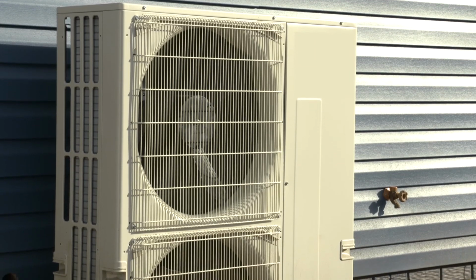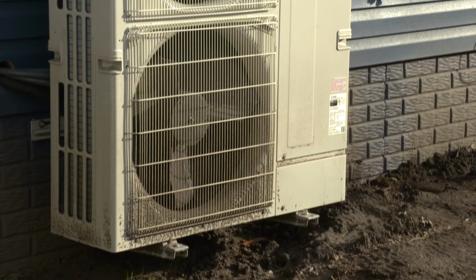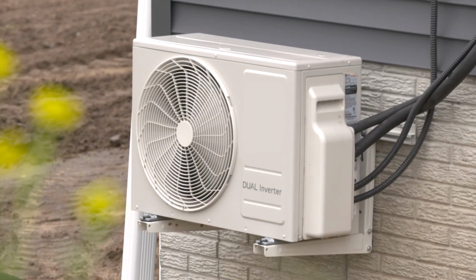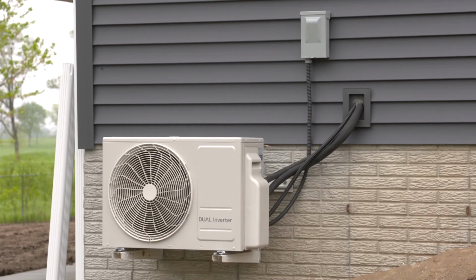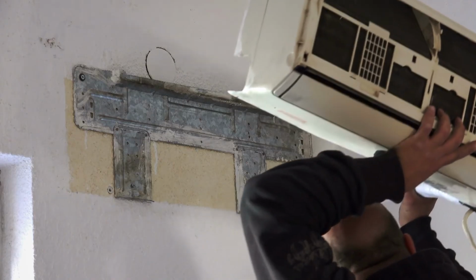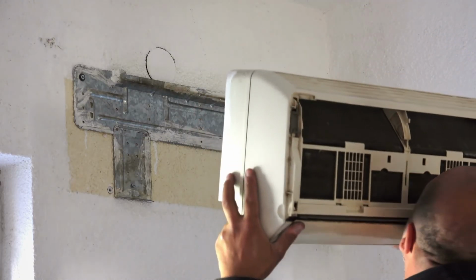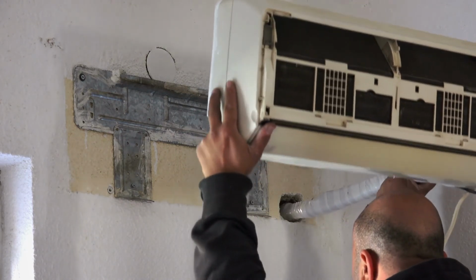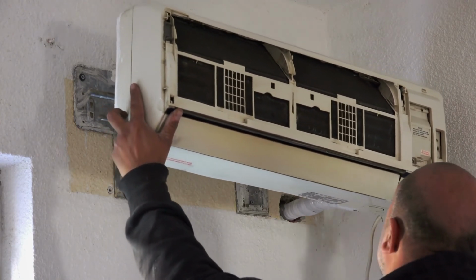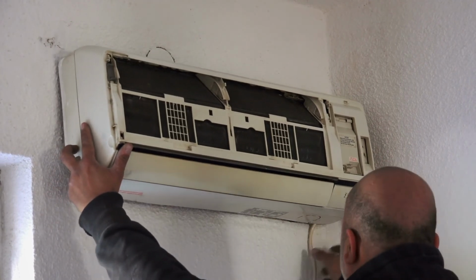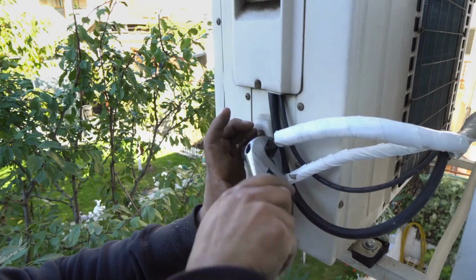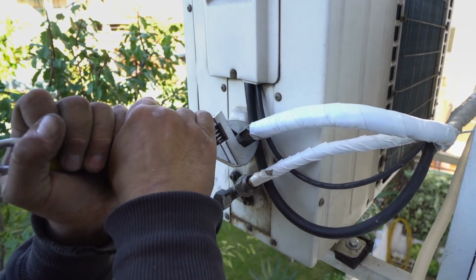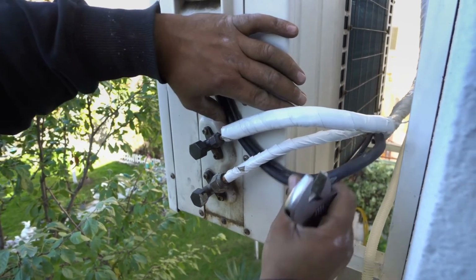Why don't you walk us through the installation process so we can get a better picture? Sure, so we'll look at where we're going to be mounting both units. On the outside of the home, where the condenser or heat pump sits, we'll either install a stand on the ground, or mount a bracket if there's a structure available — you'd see that a lot on new construction homes for air conditioners, very similar. Then we'll run our line sets, looking for a route from the outdoor unit to the indoor unit where we can run the line set, which consists of 2 copper pipes, a communication cable, and a condensate drain. Once that's run, we'll do connections on both units, do the wiring, and there are different procedures for different types of units on how we pull a vacuum on the lines and install the refrigerant. Once it's charged, we run through the proper operating procedures, do checks on it, and away you go.